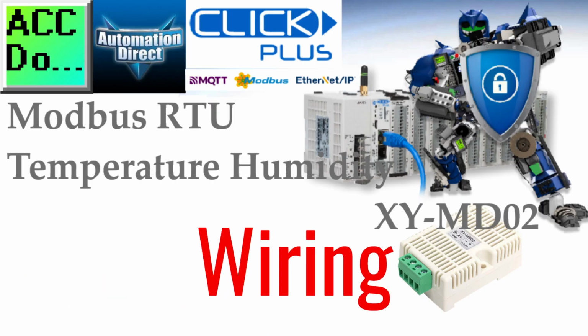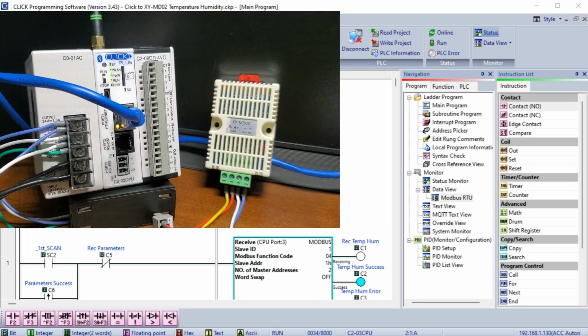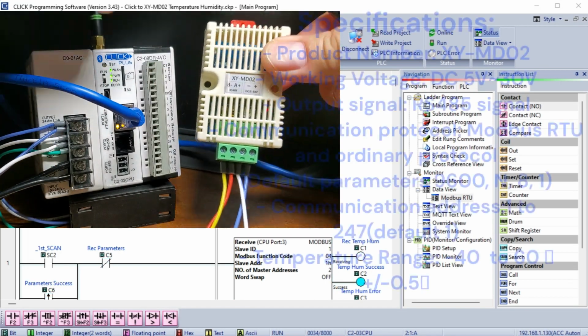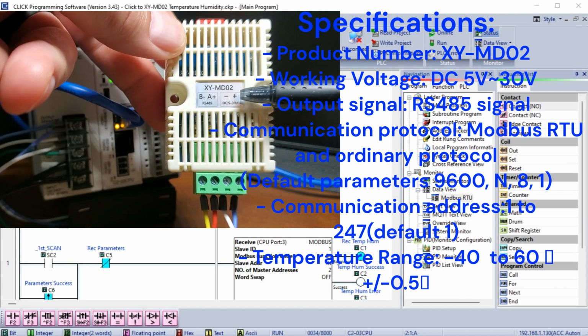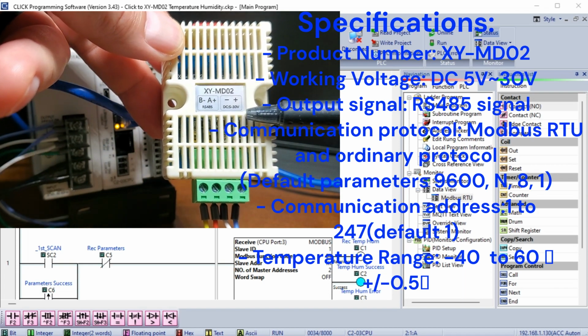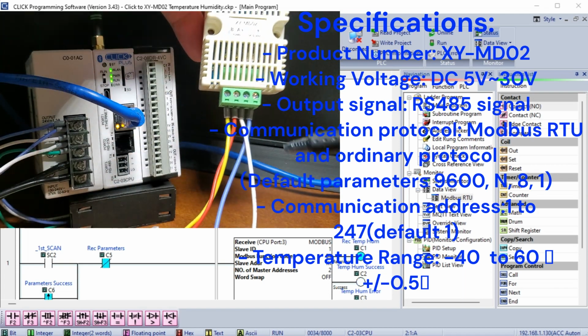Wiring the XY-MD02 to the Click PLC. This temperature and humidity sensor is powered by the DC supply. The voltage can be anywhere from 5 to 30 volts DC. In our case, we are using the 24 volt DC supply for the Click PLC.